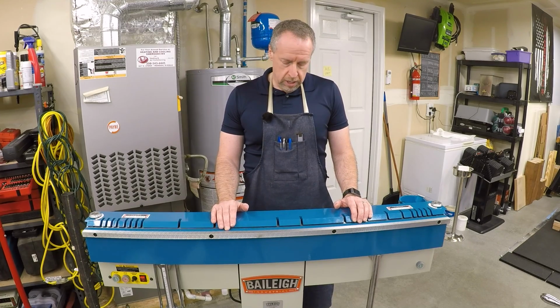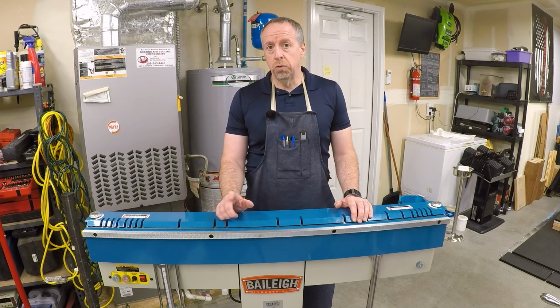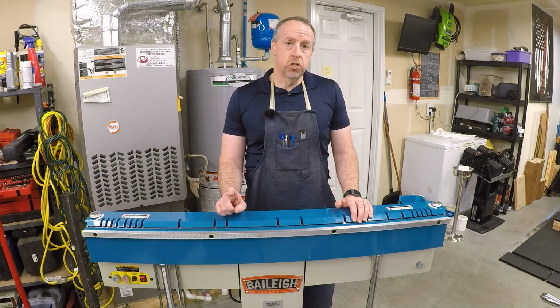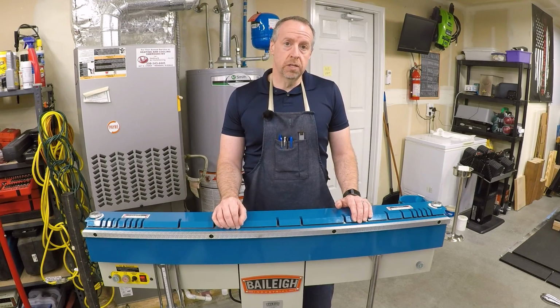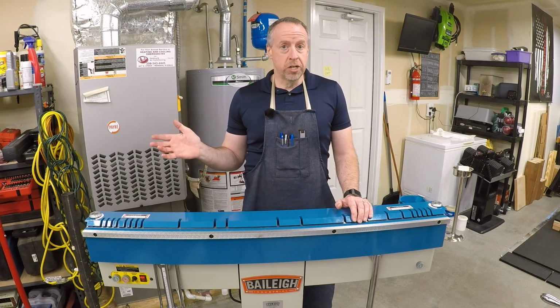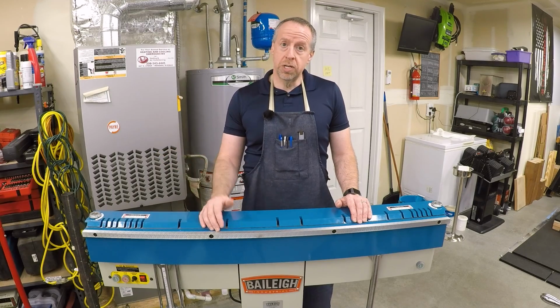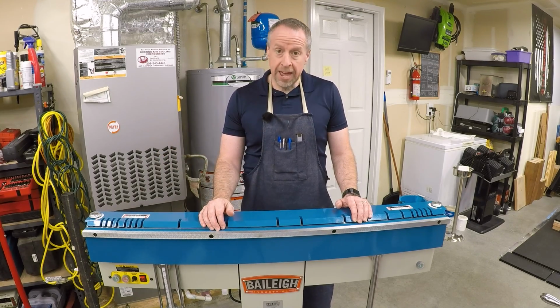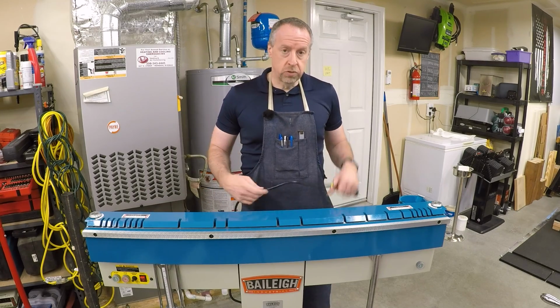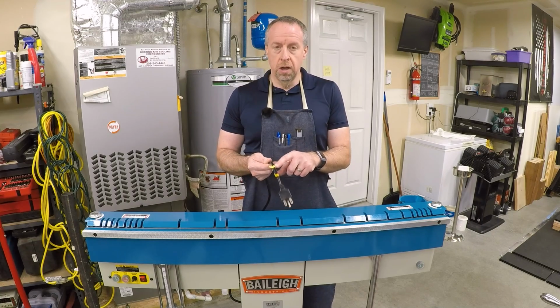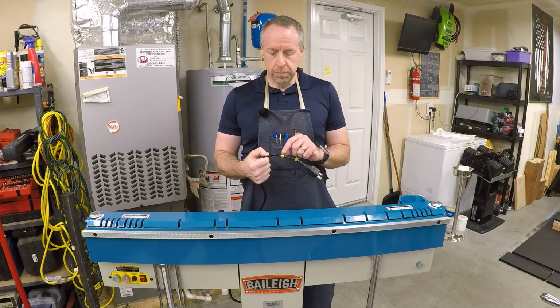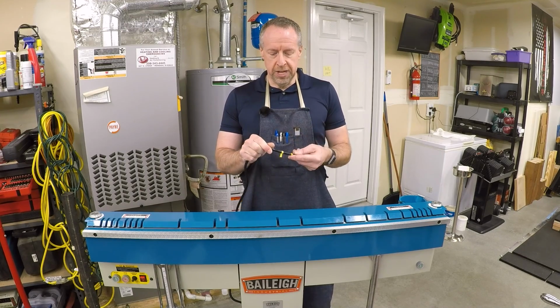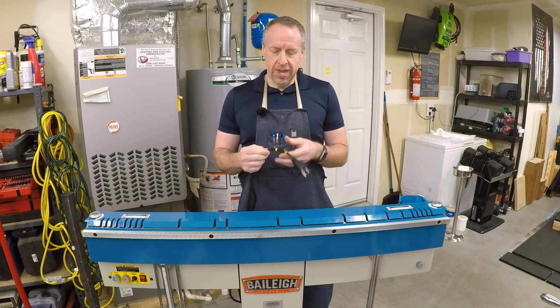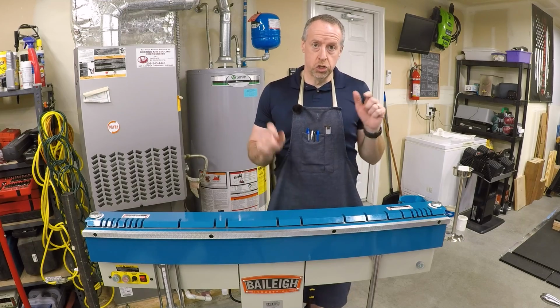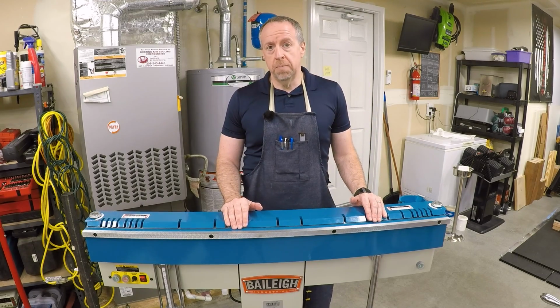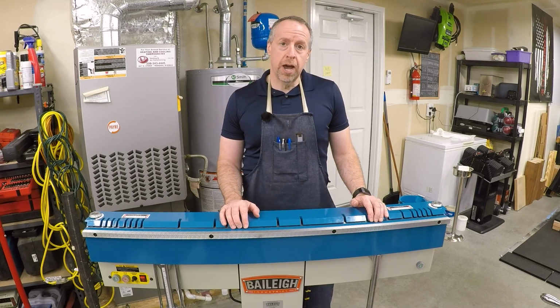The one thing about this that was really interesting is that the manual and website are both super clear about the voltage requirement: 220 volts AC plus or minus 5%, so a maximum of 231 volts. Power in my shop is 240 volts nominal, and most days it's about 244, which is too high and outside the spec. When I opened it up, they actually had a custom sticker on the power cable saying '220 volts plus or minus 5% only,' and another saying 'input power 220 volts, 60 hertz.' They've gone to a lot of trouble to make clear it's 220 volts only, and the manual and website both note that the warranty is void if you run it on higher voltages.